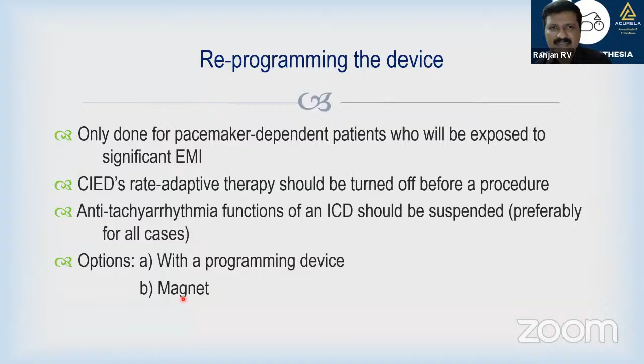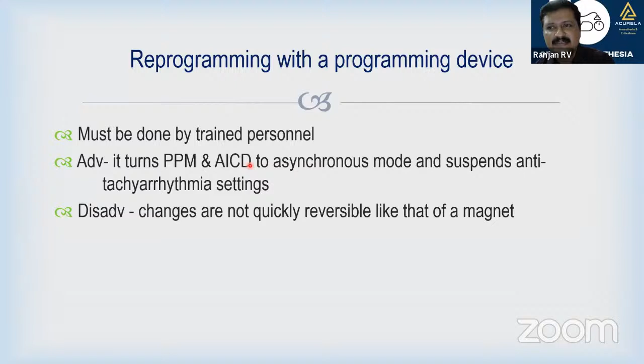AICD has two functions. One, anti-tachyarrhythmia, another pacing. Only the reprogramming device converts the AICD into asynchronous mode. Magnet will not convert the AICD into asynchronous mode. It will only suspend the anti-tachyarrhythmia function. Okay. So with the magnet, a pacemaker produces asynchronous pacing, AOO, DOO, or VOO. It suspends only the anti-tachyarrhythmia function of the AICD, not the permanent pacemaker function in the AICD. Right? So basically, it converts into asynchronous mode.